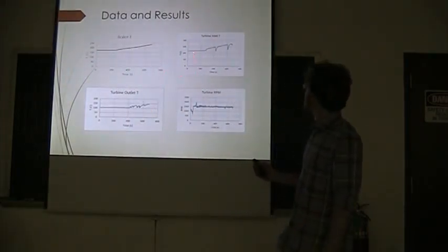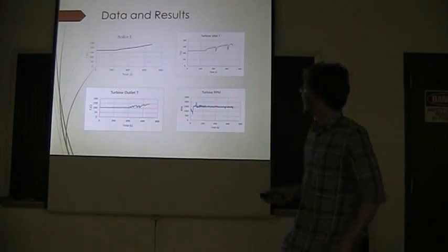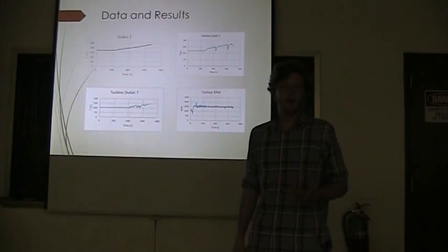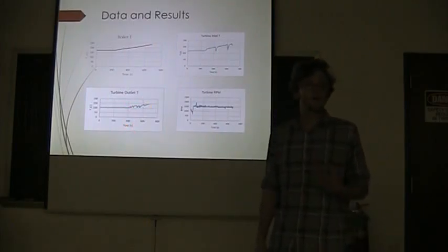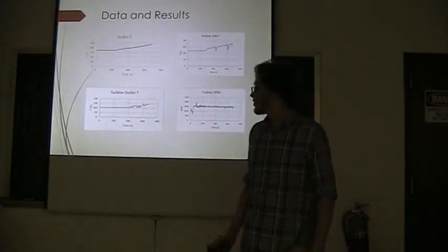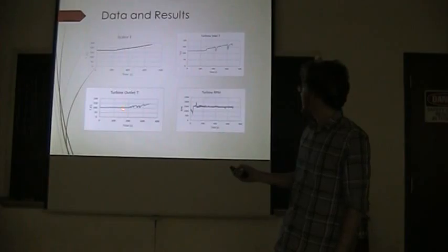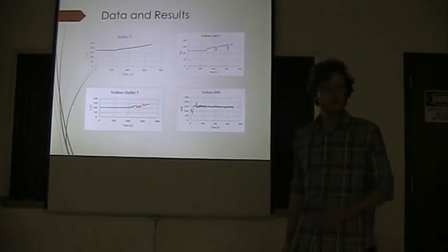But it also makes the system less stable, as we can see by some of the notable dips in here. And the outlet temperature also increasing, as we can see here, means that it's not taking out necessarily more heat than it would be just at steady state. And also, from these jagged edges here and here, the system's less stable.